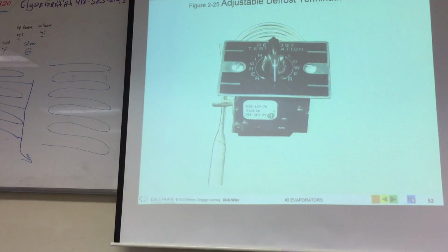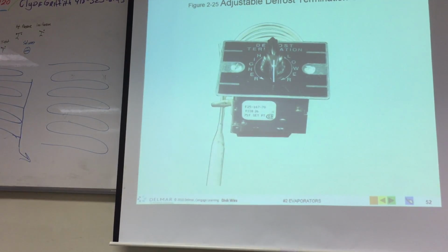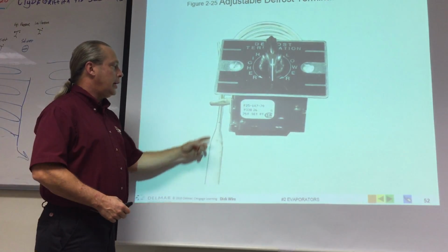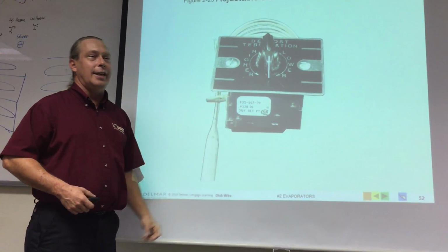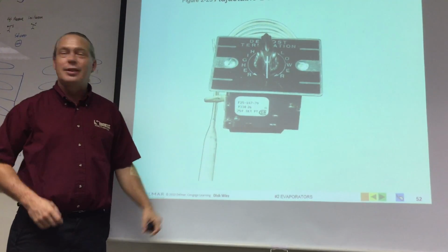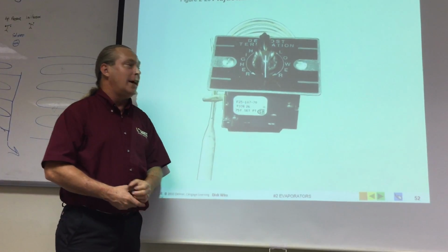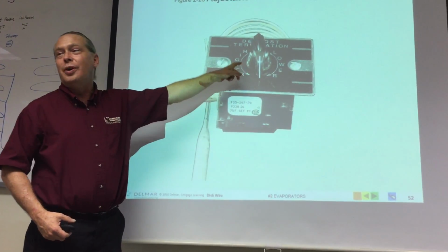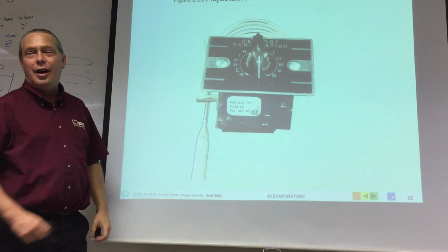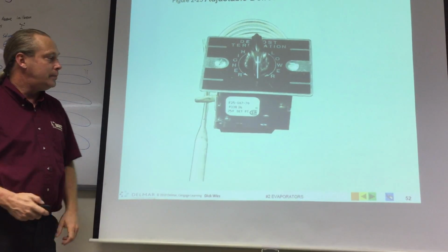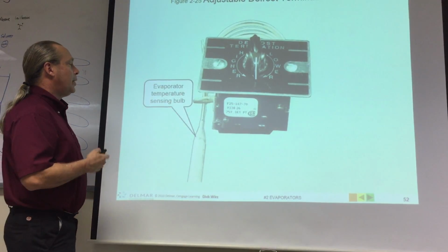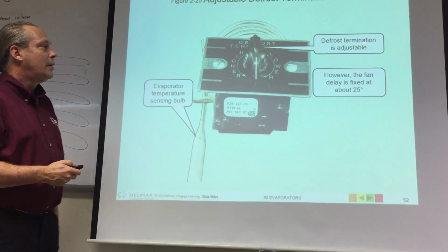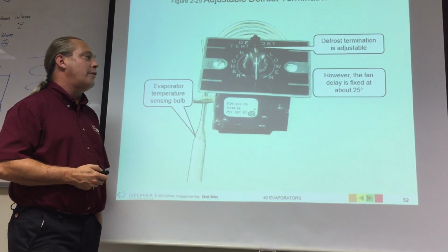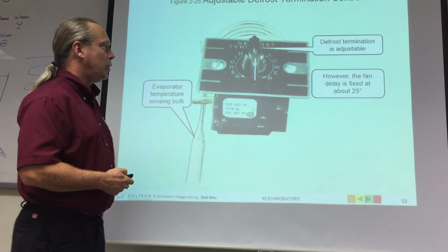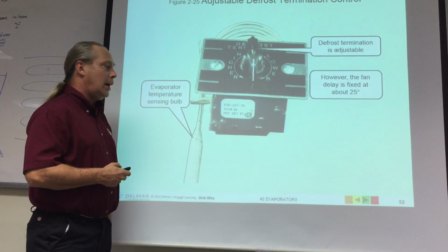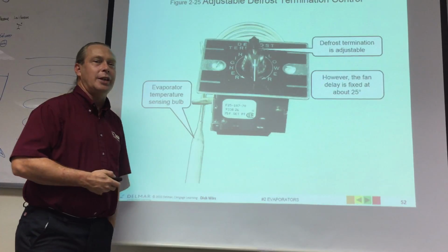And that adjustable defrost termination control is going to weigh against its opening force, and then the force that you're probably adjusting, the spring or position of the control in there. Evaporator temperature sensing bulb, defrost termination adjustable. However, the fan delay is fixed at about 25 degrees. So this is a combination, but you can't adjust the fan delay.